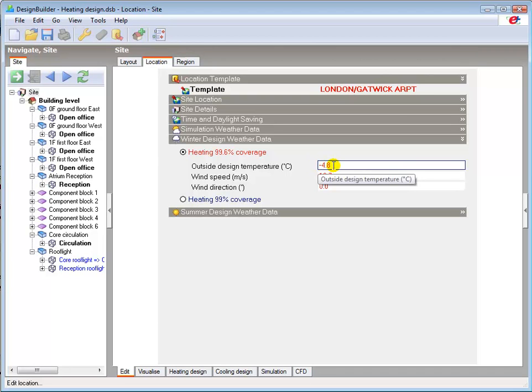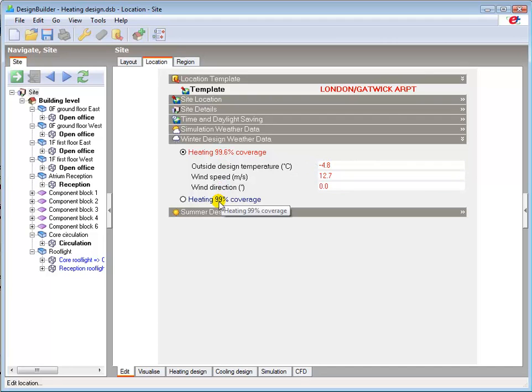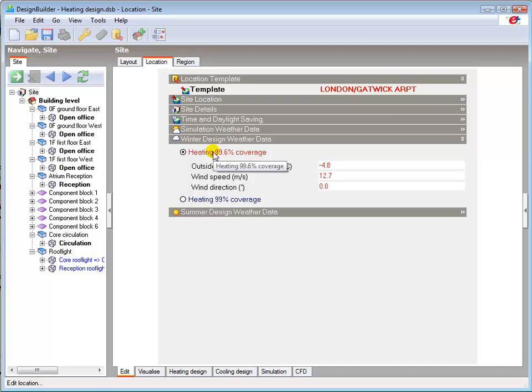You can select either the 99.6 or 99% confidence level in the design data here. Selecting 99.6%, a higher confidence level, means that there will be a 0.4% chance of more extreme winter weather occurring.